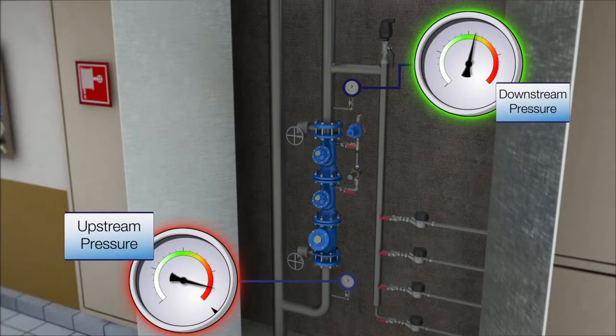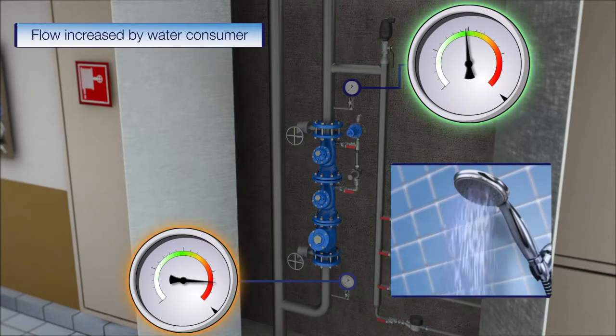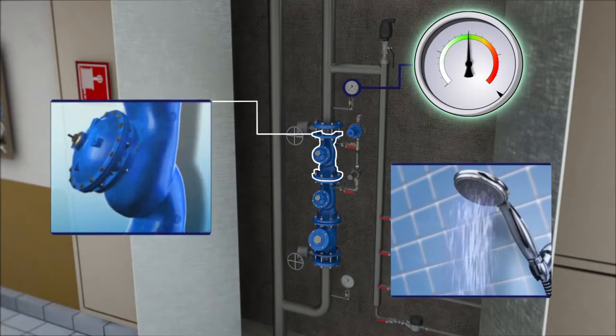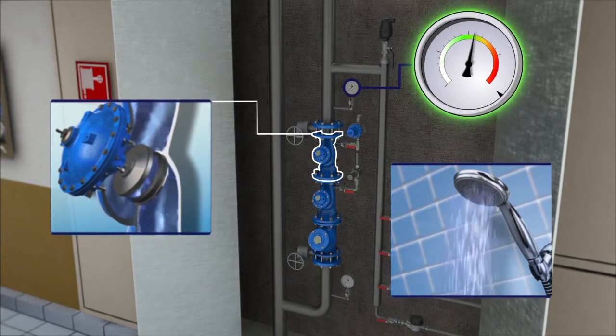At this stage, the residents do not use water and the pressure is stable. When the residents start using water, the flow increases and the downstream pressure drops relative to the flow rate increase. The pressure reducing valve increases the pressure until the downstream pressure is back to normal level.